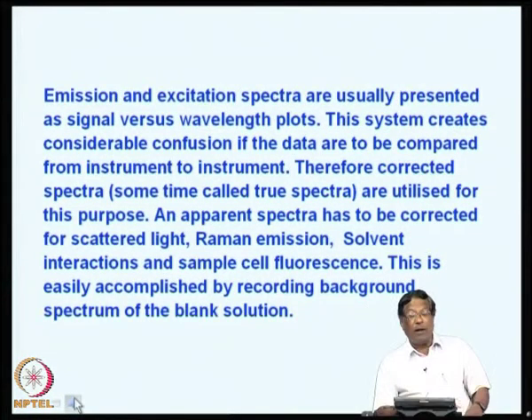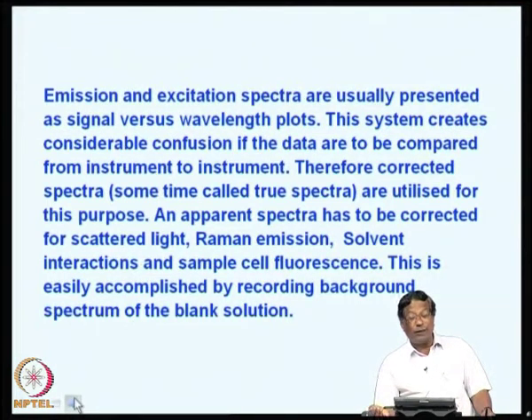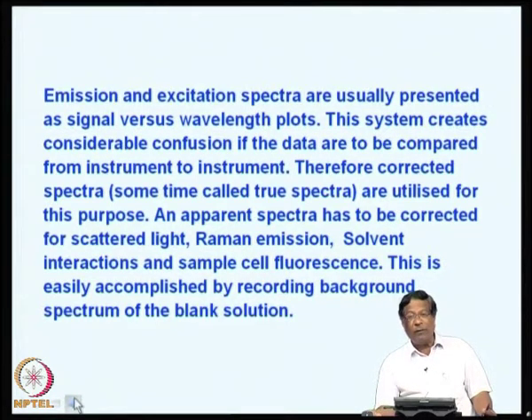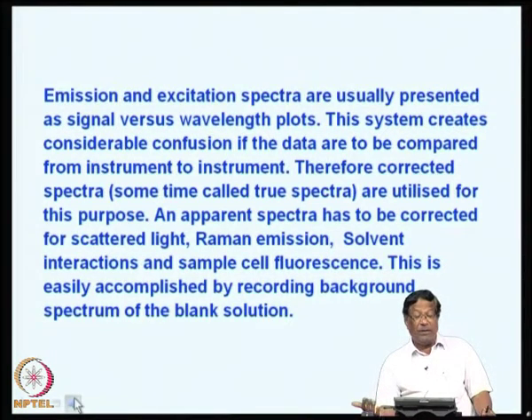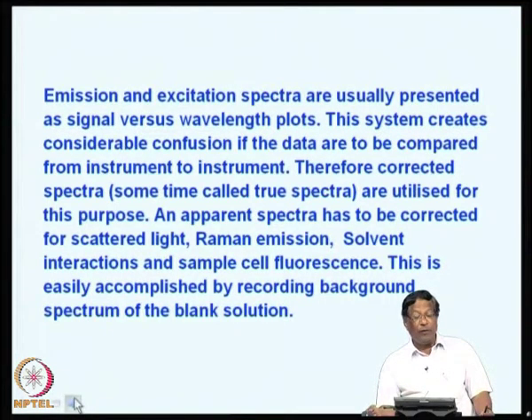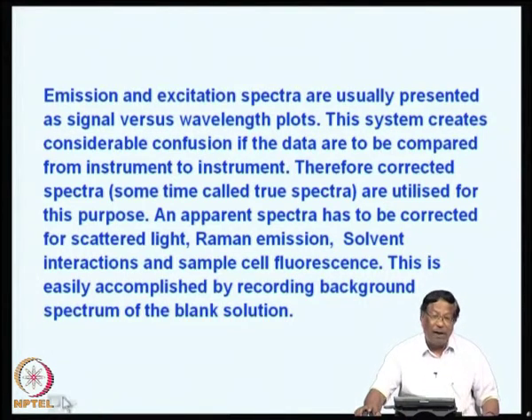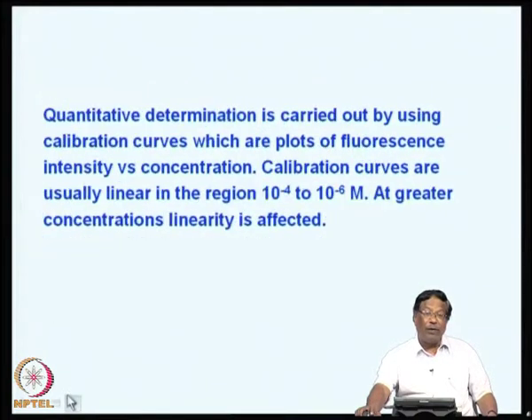Emission and excitation spectra are usually measured and presented as signal versus wavelength plots. This creates considerable confusion if the data are to be compared from instrument to instrument. Therefore, corrected spectra — sometimes called true spectra — are utilized for this purpose. An apparent spectrum has to be corrected for scattered light, Raman emission, solvent interactions, and sample cell fluorescence. This is easily accomplished by recording the background spectrum of the blank solution and then subtracting it from the sample fluorescence.